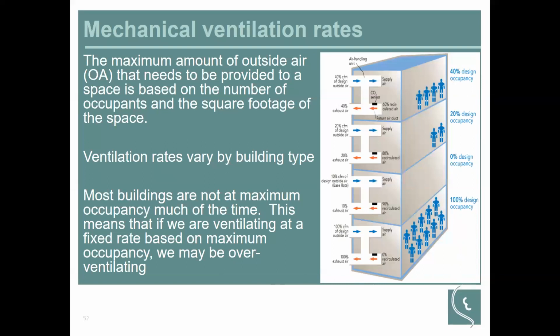Most buildings are not at maximum occupancy most of the time. And if we have a fixed ventilation rate, then we may be over-ventilating our spaces. If energy were free, if energy consumption didn't have any consequences, well, then that might be okay. But there's consequences. It costs extra money to over-ventilate a space, and it's just not necessary. So we're seeing more and more demand control ventilation, where we're actually modulating the amount of outside air that we're introducing into a building based on the number of occupants in the space or the concentration of CO2 in the air.